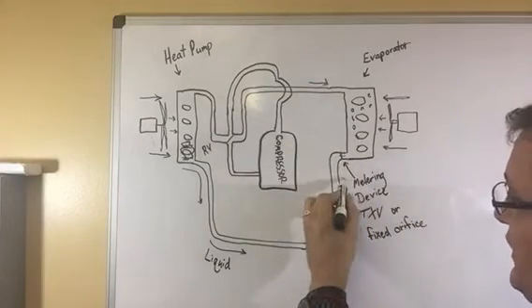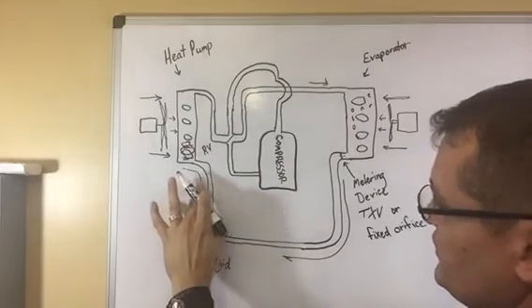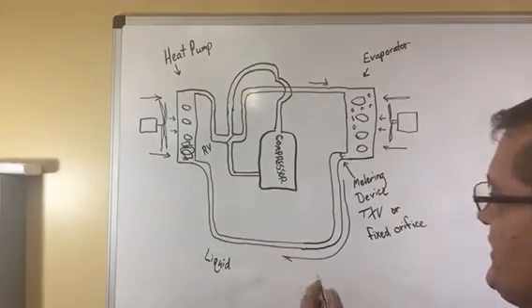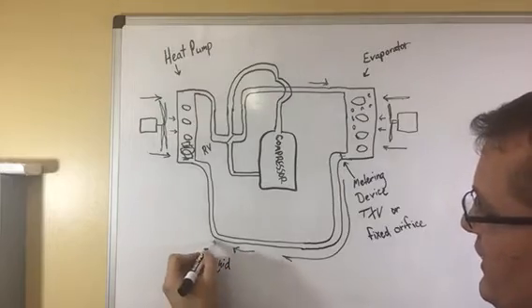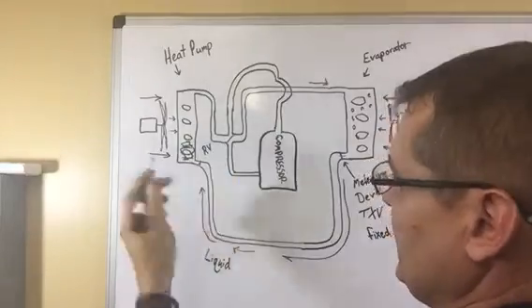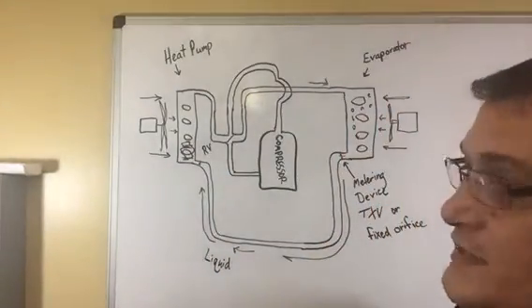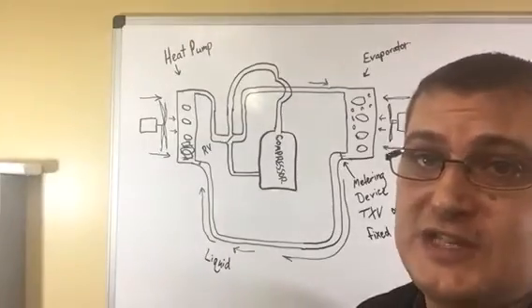So as it condenses to a liquid, it's now traveling this way. So you just reverse the flow of the refrigerant basically. So now it's traveling this way as a liquid. There's normally another metering device on the outdoor unit. It hits that metering device, sprays in there. And as it sprays, it's absorbing heat from the outside air.